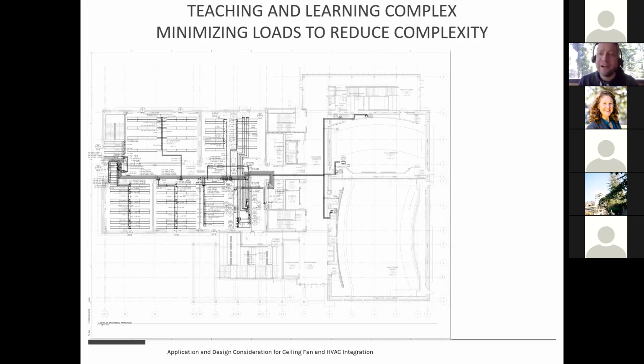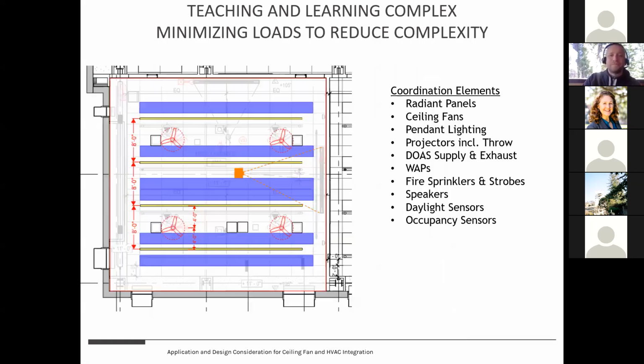So you want to work hard to reduce how many you need, which is why solar control and a good envelope matter—they let us reduce the cooling load to nearly just the internal loads from people. In this case, we got the ceiling coverage down to about 35-40% radiant panels, which is pretty good. A lot of projects typically land around 60%, which is a lot of ceiling and a lot of cost. So to keep costs down, we want a really good envelope and solar control.